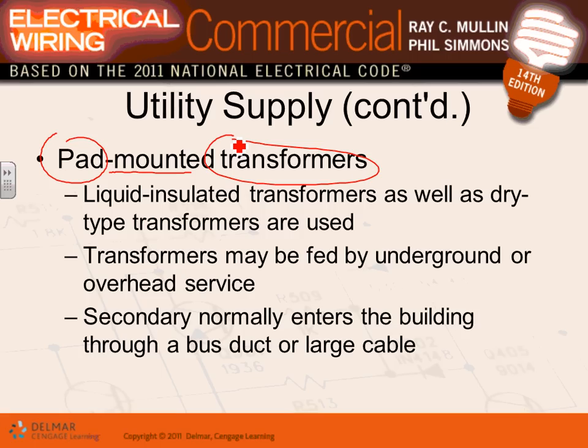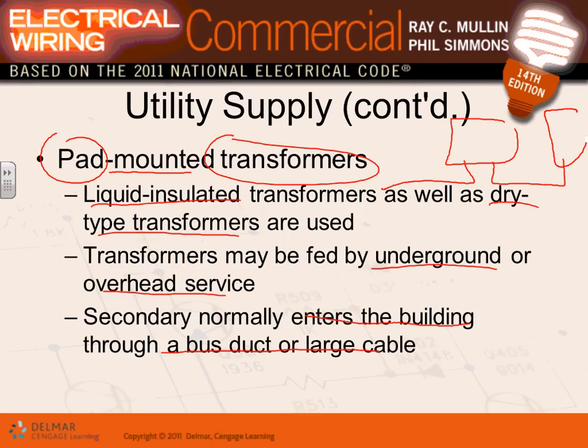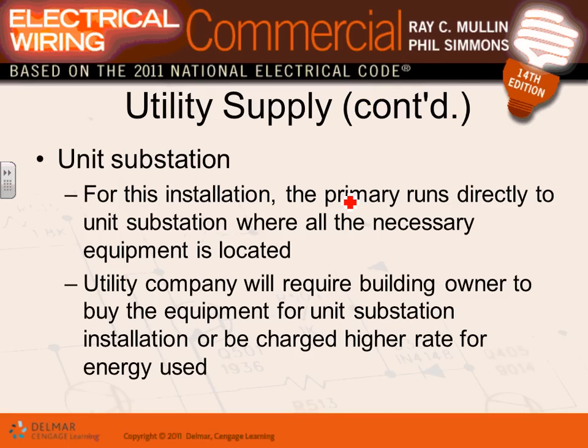They can be liquid insulated or they can be dry. As well as dry transformers. Typically dry transformers are what we prefer. Fed by underground or overhead conductors, typically underground. The secondary normally enters the building through ducts or cables. So you have your transformer coming in here and you go this way to the building and this way to the electrical utilities on the pole. That's the most common application of the utility.